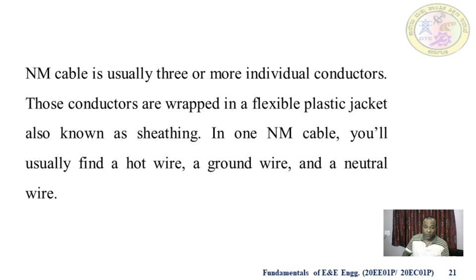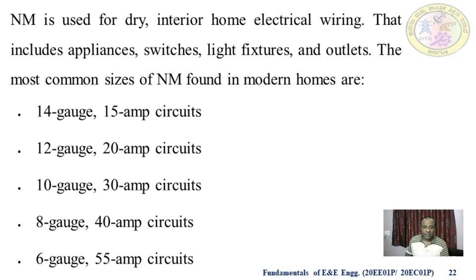NM is used for dry interior home electrical wiring that includes appliances, switches, light fixtures and outlets. The most common sizes of NM found in modern homes are 14 gauge used for 15 amp circuits, 12 gauge for 20 amp circuits, 10 gauge for 30 amp circuits, 8 gauge for 40 amp circuits, 6 gauge for 55 amp circuits. Here some of the cable ratings are given.